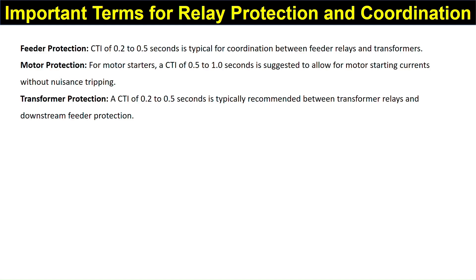For feeder protection, a CTI of 0.2 to 0.5 seconds is typical for coordination between feeder relays and transformers. For motor protection, a CTI of 0.5 to 1 second is suggested to allow for motor starting current without unwanted tripping. For transformer protection, a CTI of 0.2 to 0.5 seconds is typically recommended between transformer relays and downstream feeder protection.